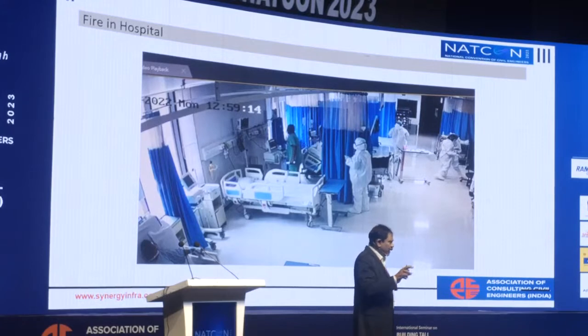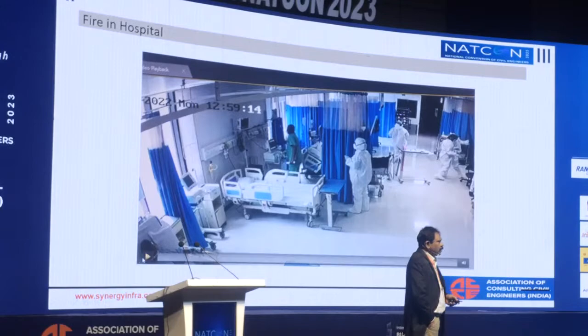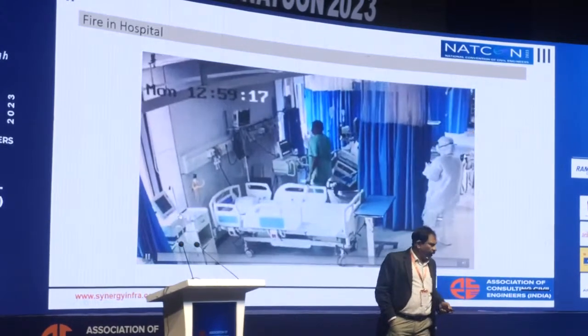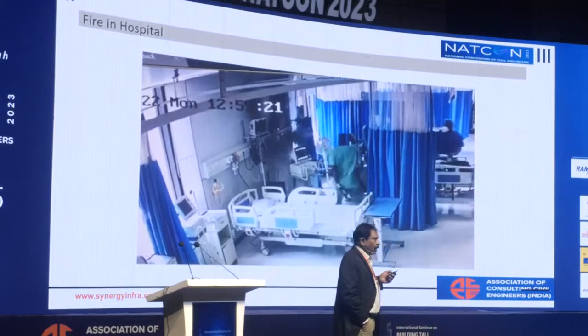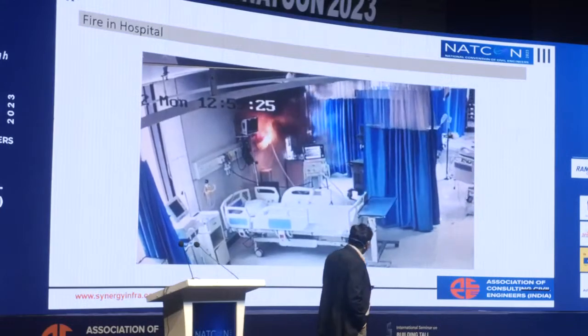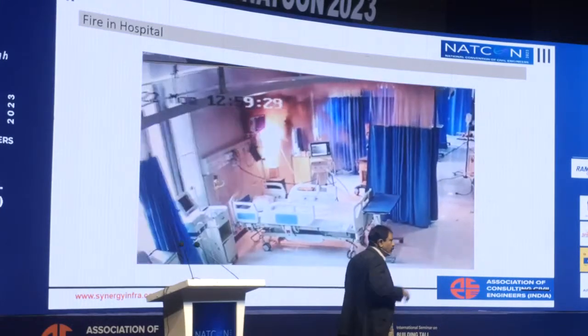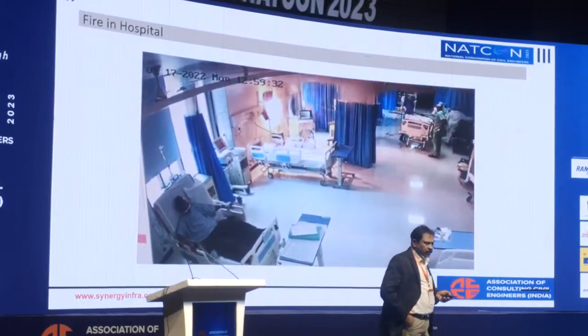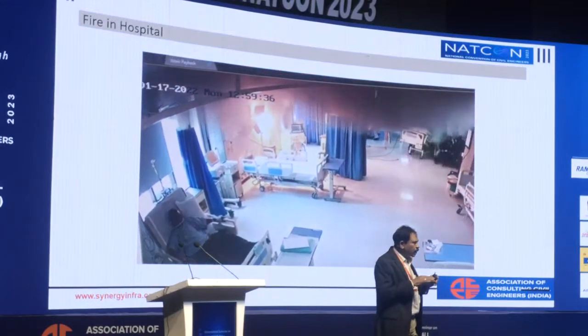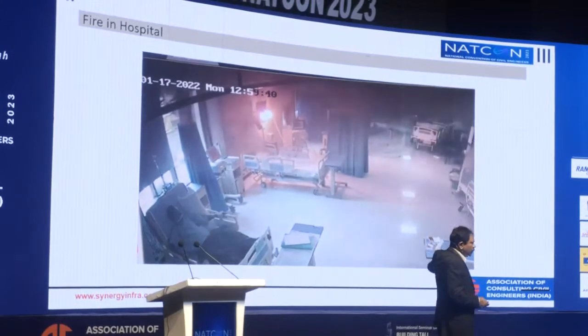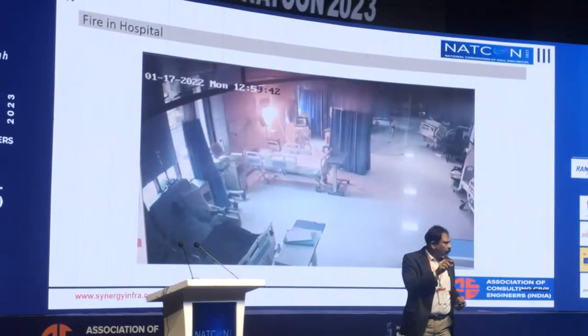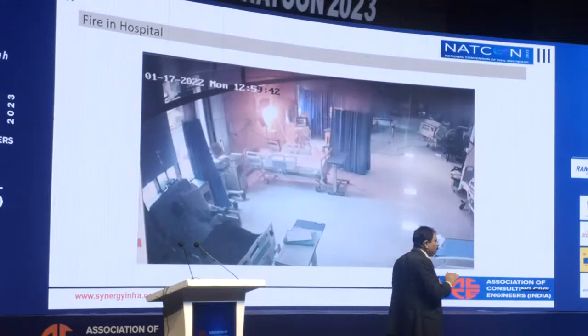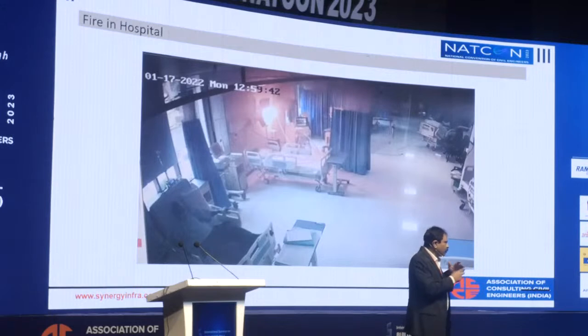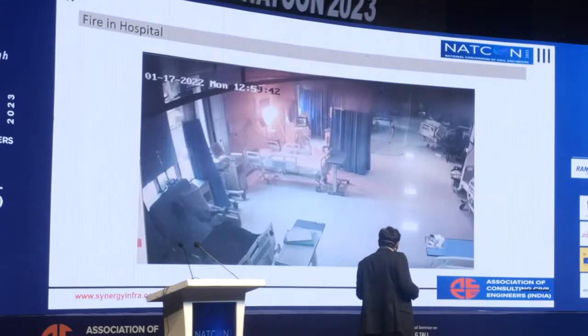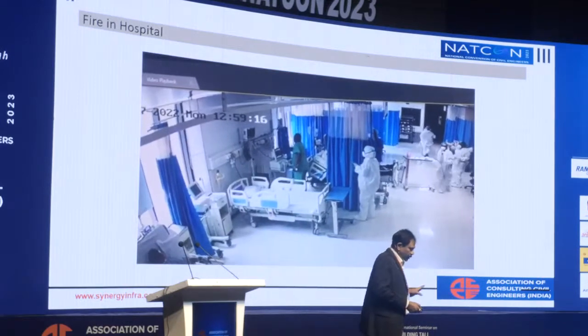Generally we use a lot of bed-head panels. In India, hospitals are restricted to a height of 45 meters, but the Government of Telangana itself is coming out with hospitals up to almost 120 meters. We don't have any testing for bed-head panels, that's what I've noticed. Whenever medical gases and electrical power lines are taken through the same bed-head panel, this happened in Hyderabad last year in one of the hospitals. As per codes we are supposed to maintain a gap of around 200 mm, but with a bed-head panel the entire panel is around 250 to maximum 300 mm, so there is no such gap and no airtight barrier between the two. It is always advisable to make sure we go for a proper system.